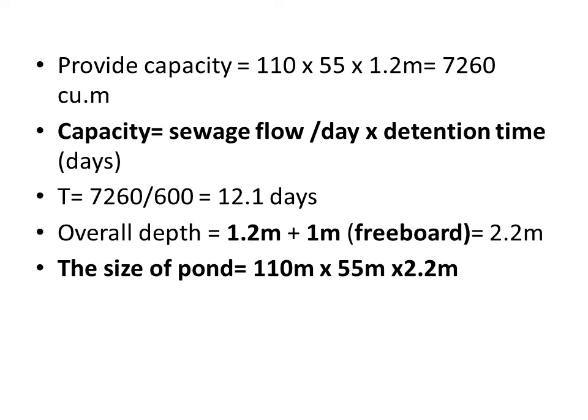For the overall depth, in addition to the effective depth, we have to provide the freeboard. For the oxidation pond, it is already given in the design criteria. You have to provide the freeboard as 1 meter. So total depth will be 1.2 plus 1 meter, that is 2.2 meter.